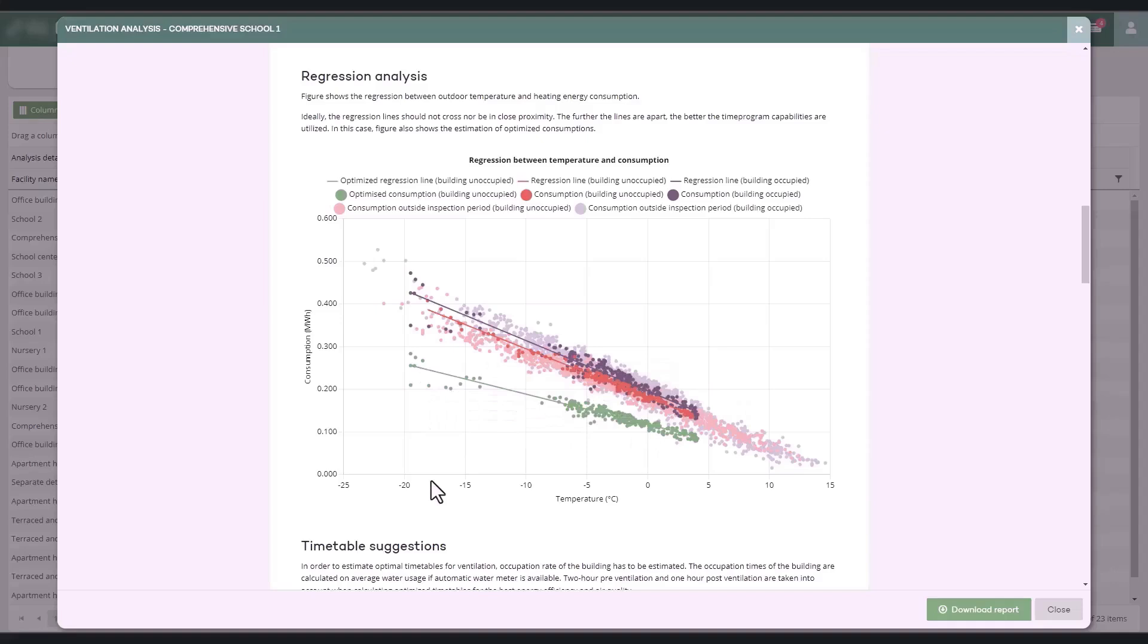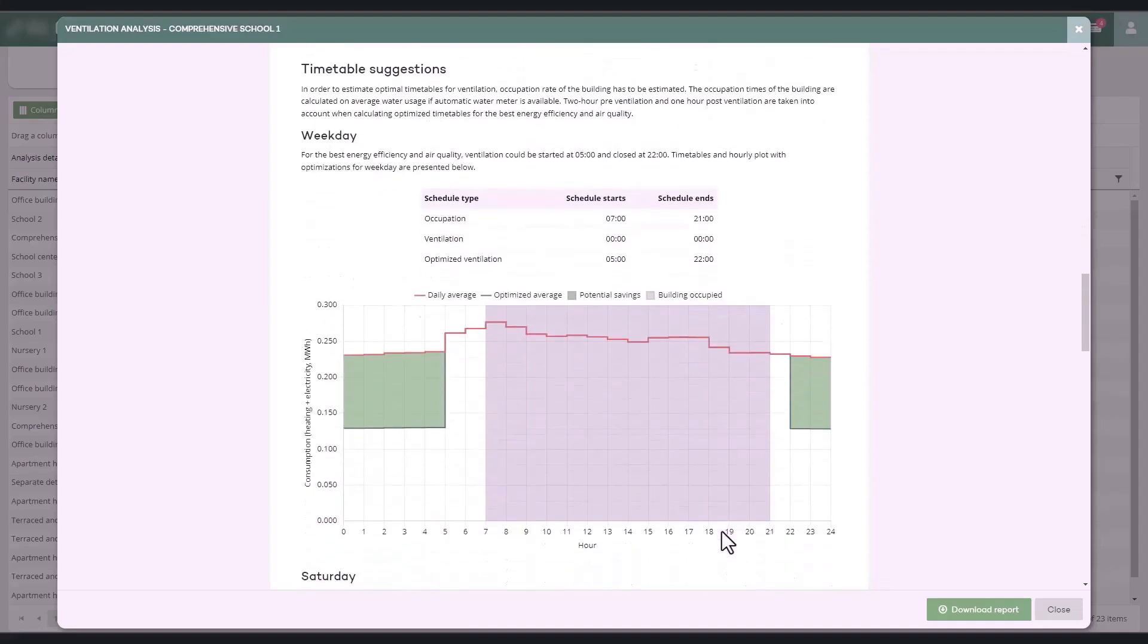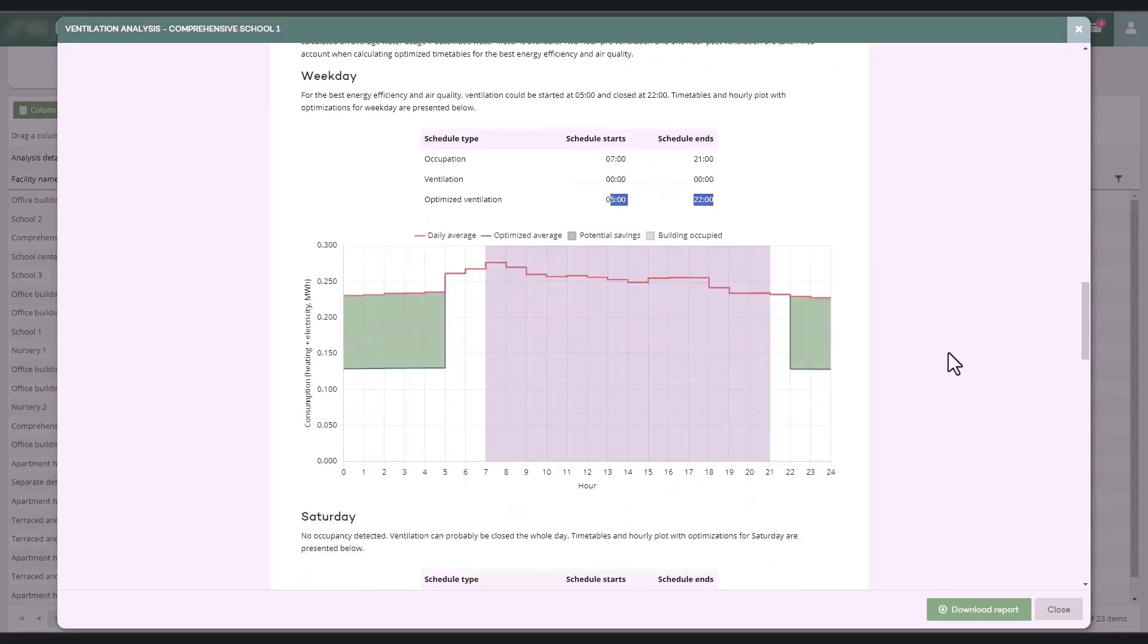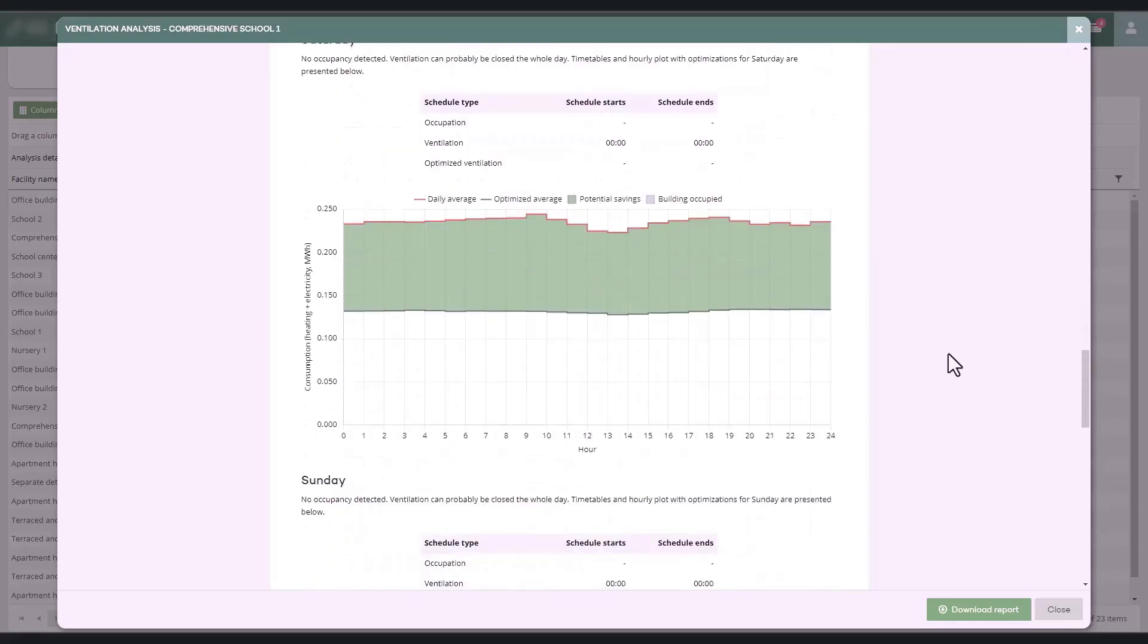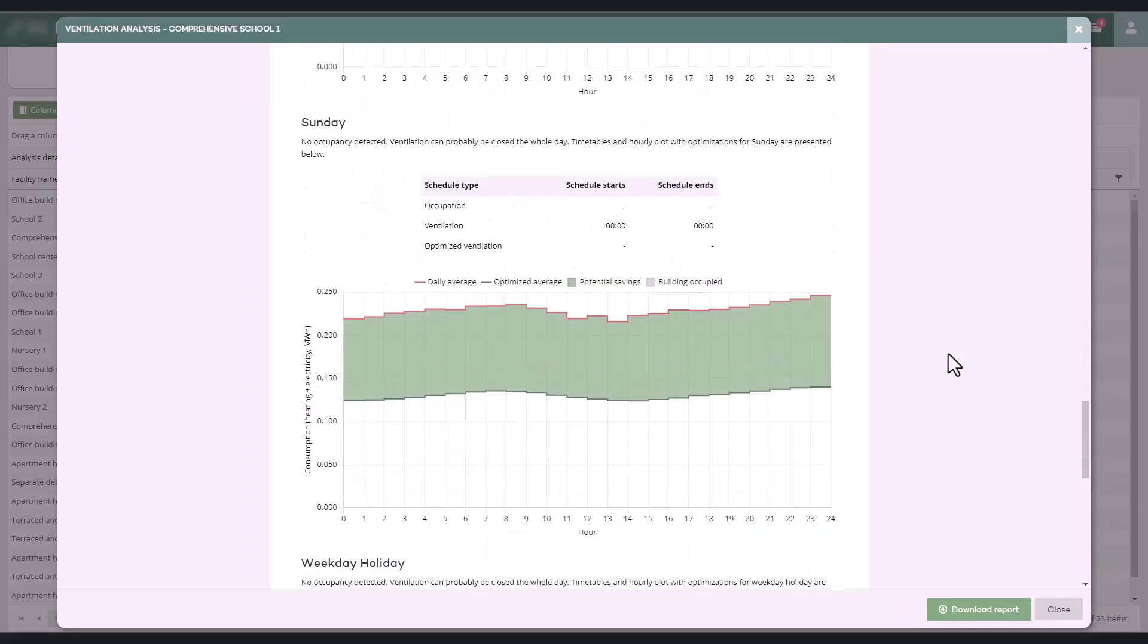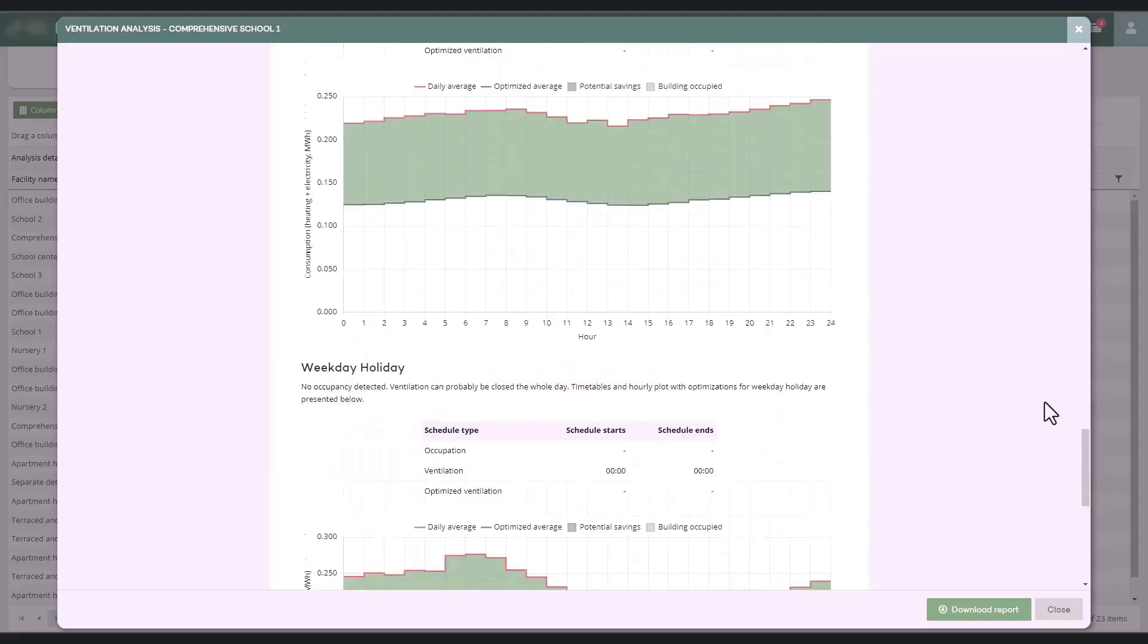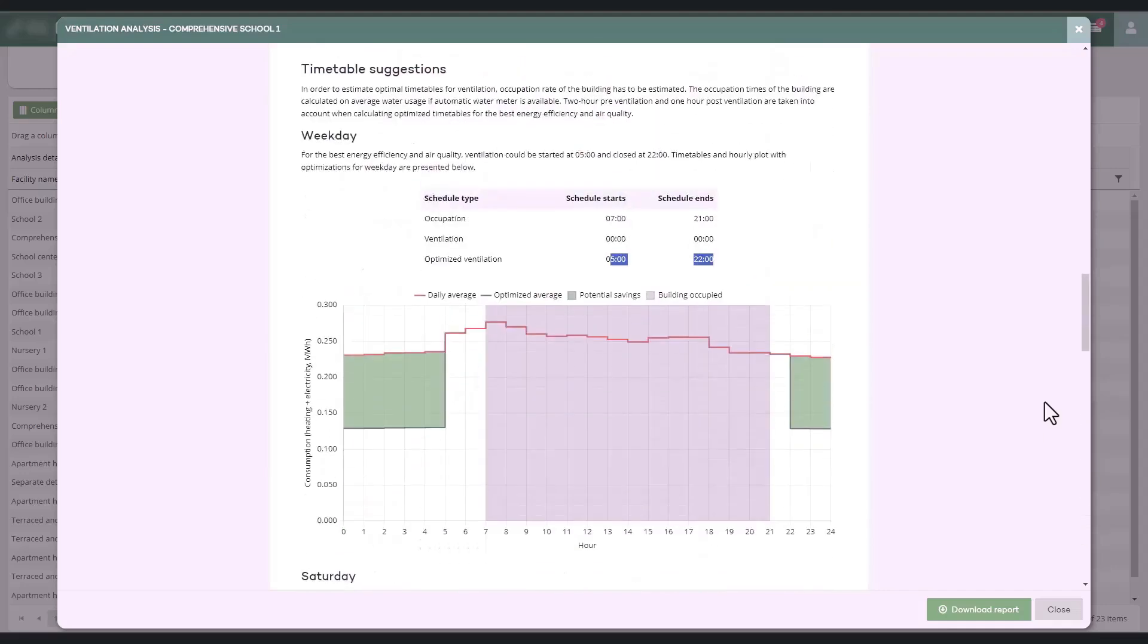In the Timetable Suggestions section, identified schedules are compared to the facility's actual usage times to analyze whether the schedules align with the operating times. The section presents proposals for the facility's ventilation time programs separately for weekdays, weekends, and public holidays. Optimal ventilation usage is based on the recommendation that ventilation should start two hours before the facility's use starts and stop an hour after the usage ends.